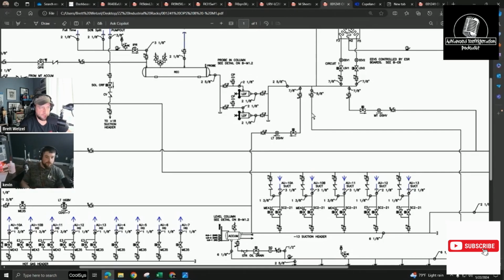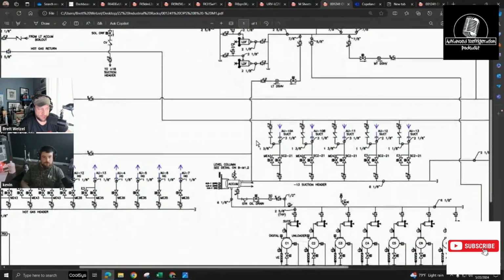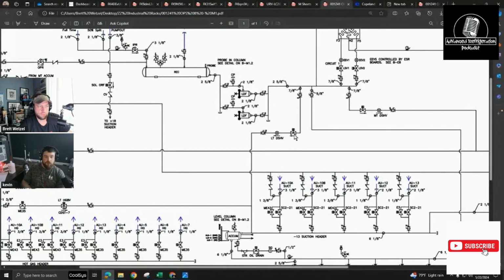This has so much stuff going on to it, because look, then you also have off the liquid line here, you have a low temp de-superheating valve. So you're pulling liquid off there, off that 7/8 line, also being able to throw it into this minus 13 degree header. Which kind of makes sense. With something that big, you're going to probably struggle to maintain low superheats on coils. This is one of those racks where 800 pounds is like not even a dent.